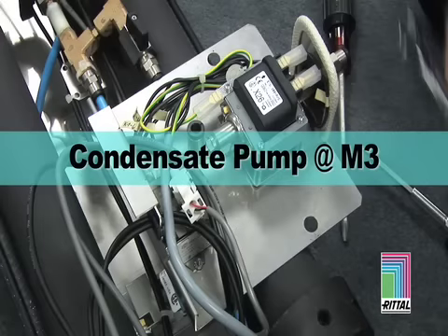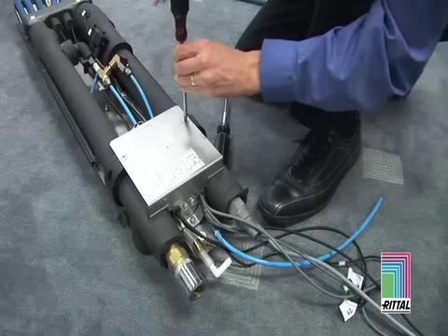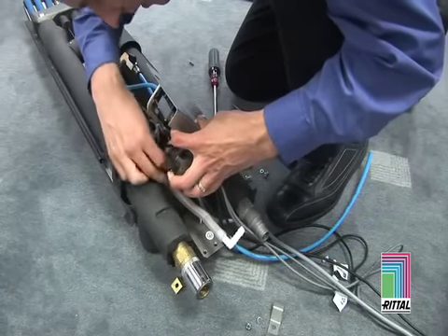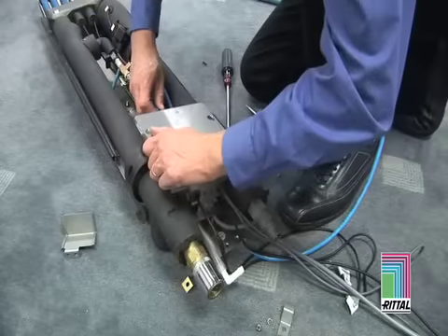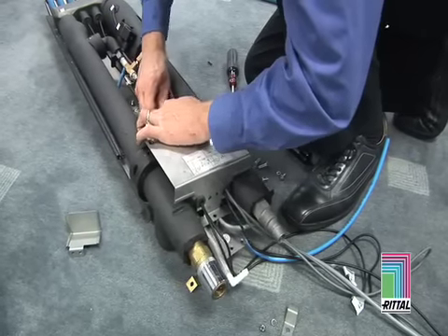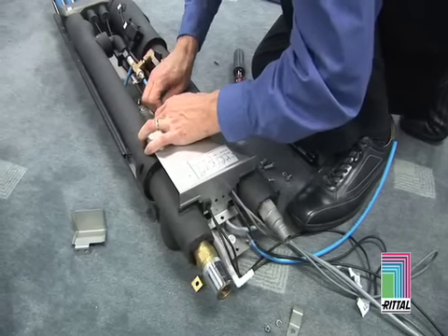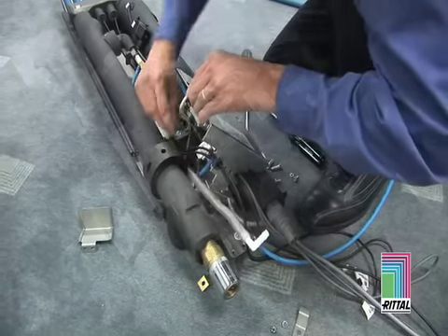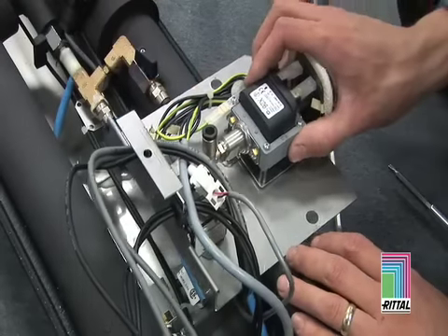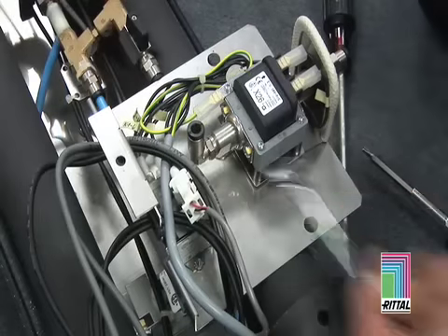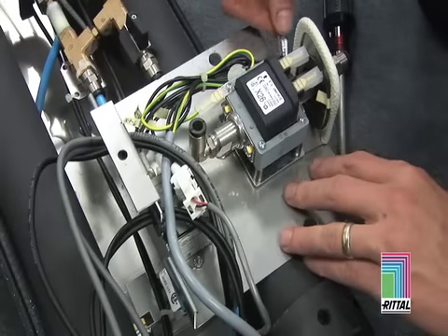Condensate pump servicing. Remove the tray screws that hold the condensate pump. Remove small blue hoses that are attached to the condensate pump. The hoses are removed by pulling the black ring forward into the body and pulling the hose out at the same time. Replace condensate pump assembly with new condensate pump. Installation is the reverse procedure.